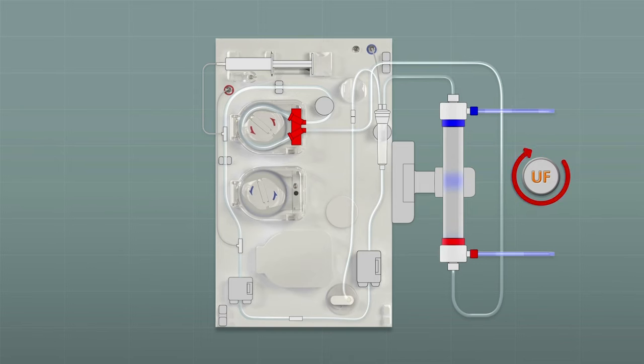The UF pump starts rotating in reverse direction and instead of removing fluid it is now delivering dialysate into the bloodline through the dialyser which acts as a second endotoxin filter.